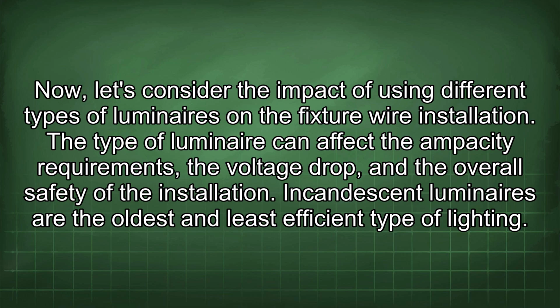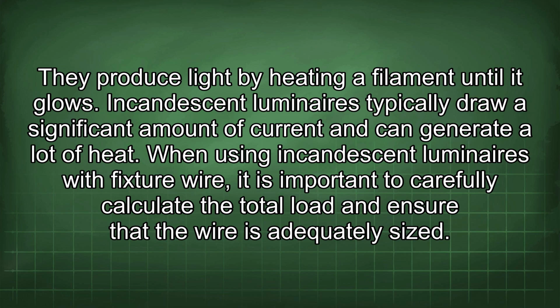The type of luminaire can affect the ampacity requirements, the voltage drop, and the overall safety of the installation. Incandescent luminaires are the oldest and least efficient type of lighting. They produce light by heating a filament until it glows. Incandescent luminaires typically draw a significant amount of current and can generate a lot of heat. When using incandescent luminaires with fixture wire, it is important to carefully calculate the total load and ensure that the wire is adequately sized.